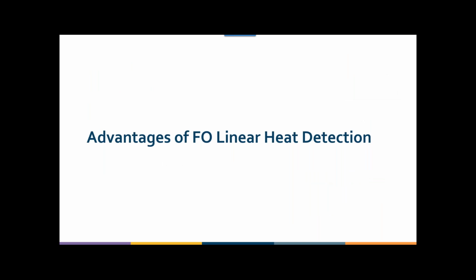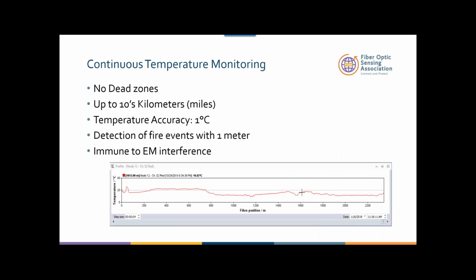The advantage of fiber optic linear detection is continuous temperature monitoring. This is one of the most amazing things: there is no dead zone. In a conventional linear detection approach, you have to set your physical zones. In this case, you don't set your physical zone.